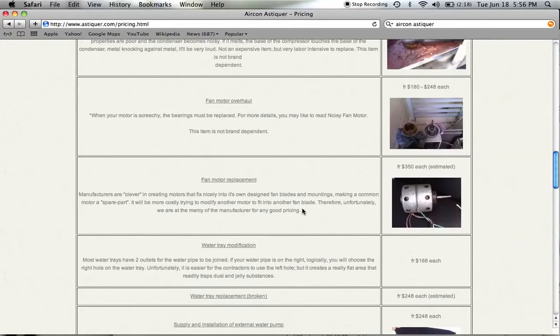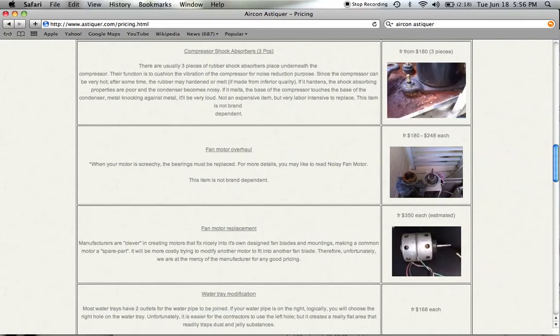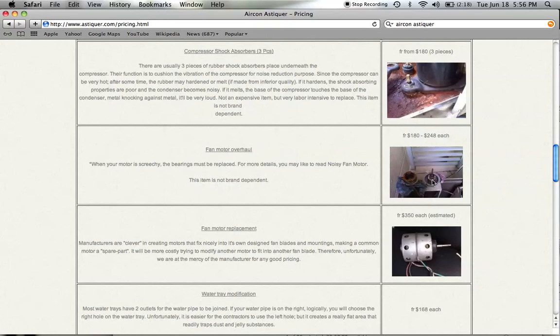I'm not too sure how much you can see from here, but this is a motor of the outdoor condenser fan. The indoor fan motor basically will look similar to this but it's a lot smaller. If we can take it apart, we can replace the bearings, and that costs about $180 to $245 to $248.